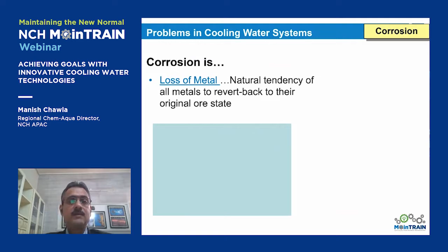Corrosion. What is corrosion? It is an electrochemical process because of which there is a loss of metal. Whenever water which has TDS and oxygen comes in contact with any metal, it will try to dissolve that metal back, causing loss of metal. Now this loss of metal could be uniform across all parts, or it could be localized. When it's localized and in the form of holes, we call it pitting.